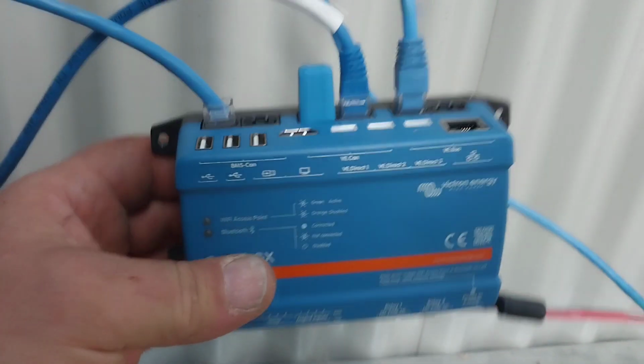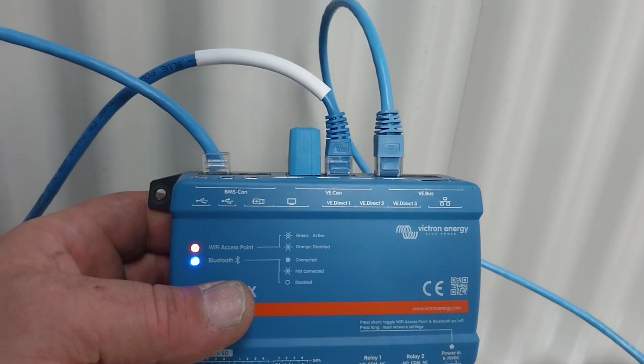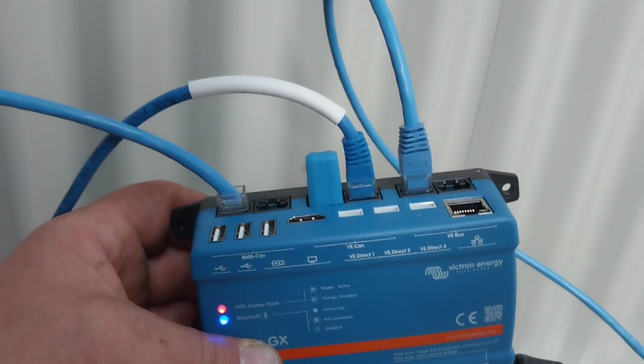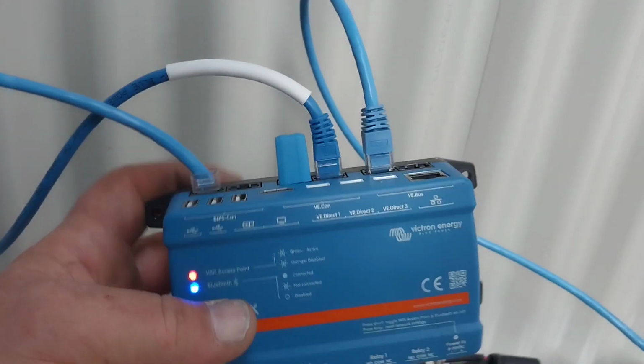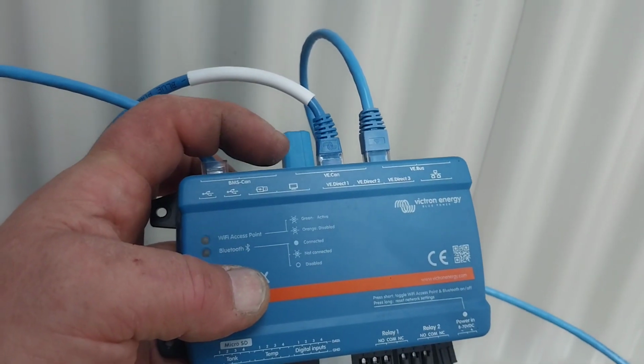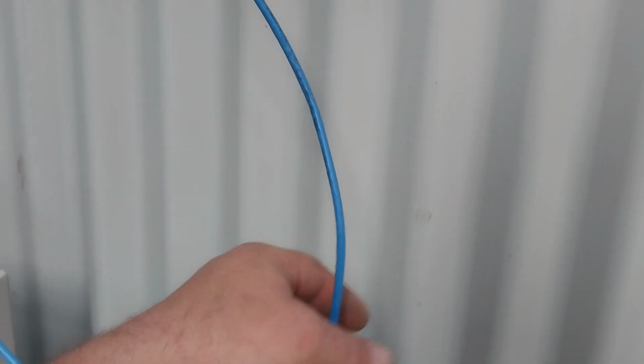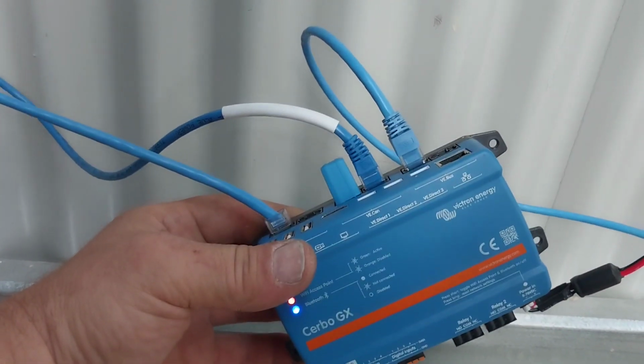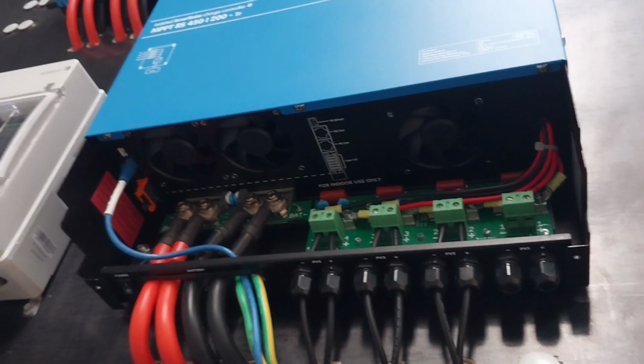So commissioning stage. So things aren't exactly tidy yet. Stuck a dummy there in the left. What's that, a VE can? Must have a little resistor in it, I assume, I don't know. Anyway, there's another one going in VE can. That's this one here to the middle, the dummy in that one. And that one, VE can, has a Victron cable called VE can. And that goes into the Victron, into that terminal there, right near the VE direct terminal, which we don't need. So that's your communication from the Cerbo GX to the RS 450-200.